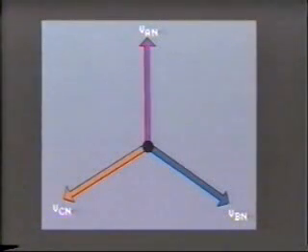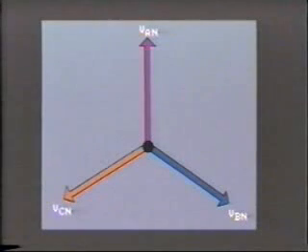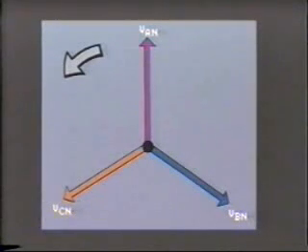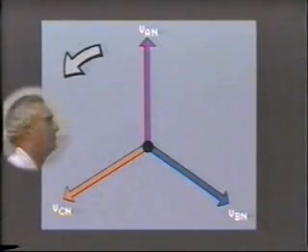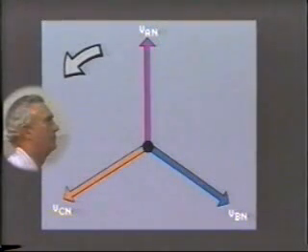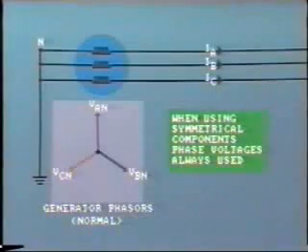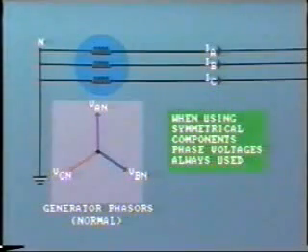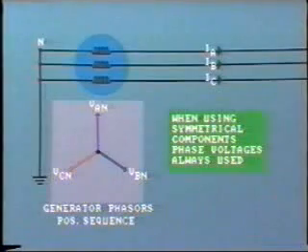Let's look at this a little closer. To begin with, we already know that a generator produces three equal voltages, which are equidistantly spaced 120 degrees apart. The phasor rotation is conventionally counterclockwise and the normal phase sequence is A, B, C. This means that for any fixed point in space, we would see voltage A, then B, then C, then A, and so on in that sequence. When studying symmetrical components, phase voltages are always used — that is, line to neutral or line to ground. We indicate the positive sequence voltages on our diagram by using the subscript 1.